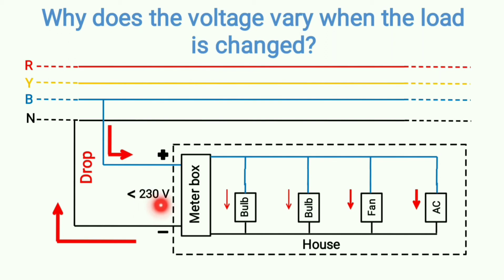If the voltage drop is increased by a large amount, your supply voltage will definitely be reduced — so whereas before it was 230 volts, now it is less than 230 volts. If this voltage reduction stays within the range of plus or minus six percent, it's fine. But if it decreases beyond that limit, we need to perform voltage control techniques, which I've already discussed in one of my videos.